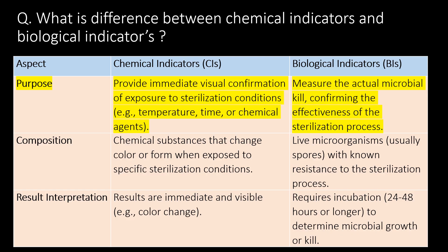A very basic and commonly asked question: what is the difference between chemical indicators and biological indicators? Chemical indicators provide immediate visual confirmation of exposure to sterilization conditions, such as temperature, time, or chemical agents, whereas biological indicators measure the actual microbial kill, confirming the effectiveness of the sterilization process.